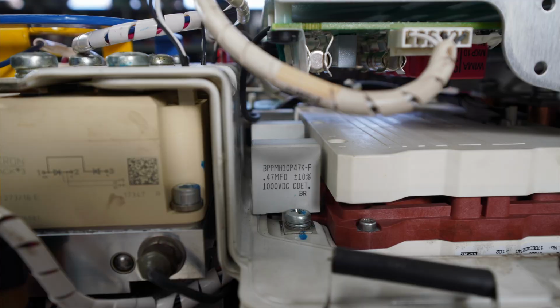So on the other side of that, when we're applying it to a VFD, we're using it as a proper rectifier. The rectifier is when we're removing part of the sine wave out of AC current. So as you come into your VFD, one of the first components that power will hit is your SCR bank, and typically each leg of power will have its own. We're going to pass through that SCR in order to remove or rectify part of the sine wave.